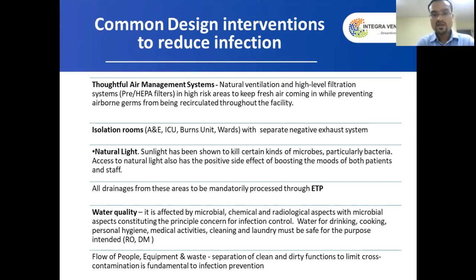The filtration has to be done according to the areas. For example, in operation theaters where we do high-end surgeries, we need HEPA filters installed. In other places like ICU, we need at least pre-filters or microvee filters. Apart from filtration and pressure gradient, we also need treated fresh air areas. These are very important to prevent and control infection.